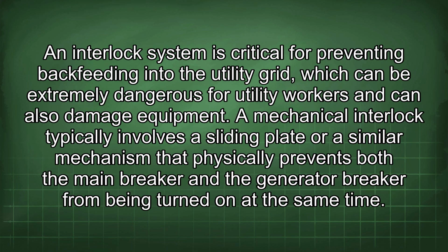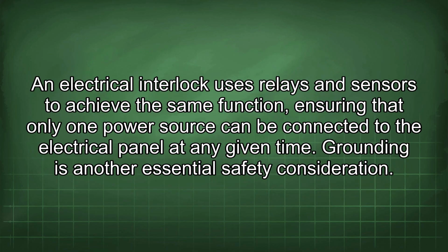An interlock system is critical for preventing backfeeding into the utility grid, which can be extremely dangerous for utility workers and can also damage equipment. A mechanical interlock typically involves a sliding plate or a similar mechanism that physically prevents both the main breaker and the generator breaker from being turned on at the same time. An electrical interlock uses relays and sensors to achieve the same function, ensuring that only one power source can be connected to the electrical panel at any given time.